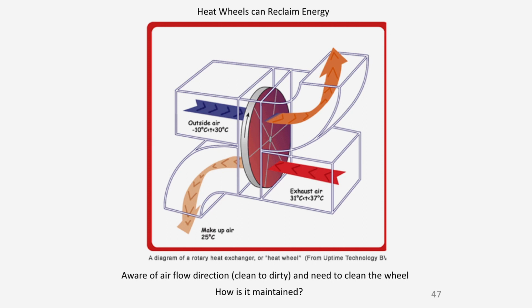Now, the trick with heat wheels is to make sure we know which way the pressures are, and that's very easy to do and has been done. So we want to watch pressure. Thinking of clean to dirty, we want the clean side of the air to be going into the dirty side as it's being discharged. And certainly we are concerned that when they clean those coils or when they recharge them, they do it in a fashion that's reasonable. And I believe they thermally clean them, which really gives us an opportunity to kill what's on those surfaces.